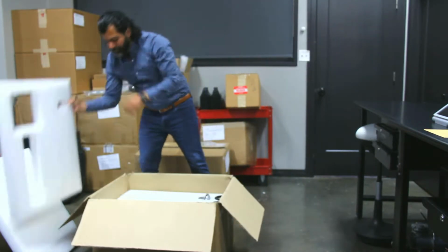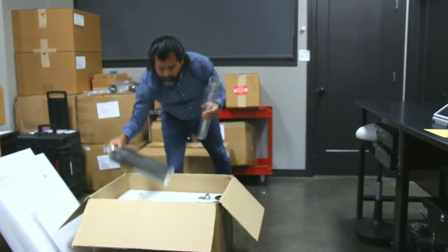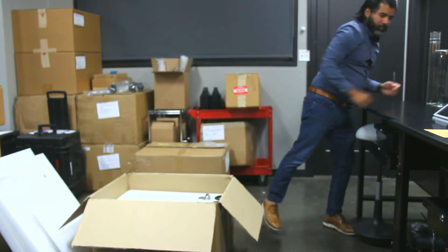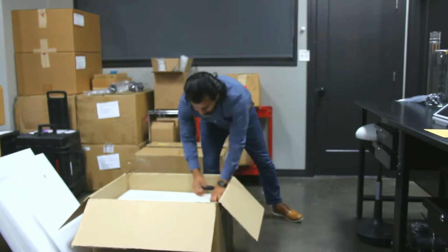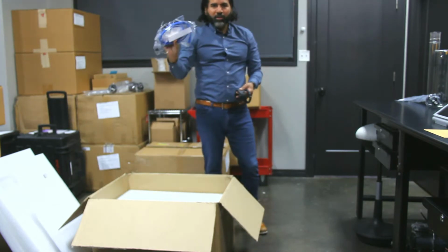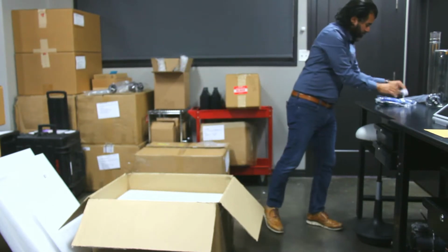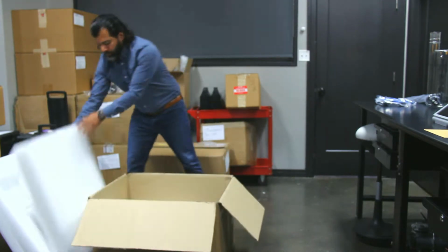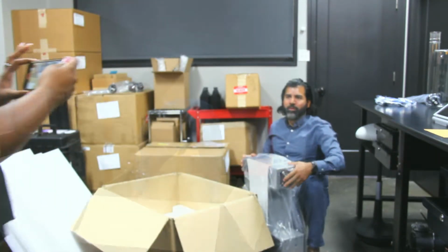Remove the second foam protection, and carefully remove the glassware. This will be used in the next step of installation, along with the connection cables. In addition to the foam packing, the unit is secured with a plastic housing.